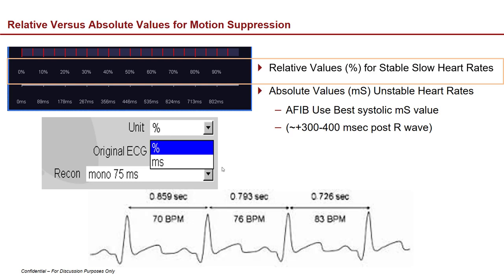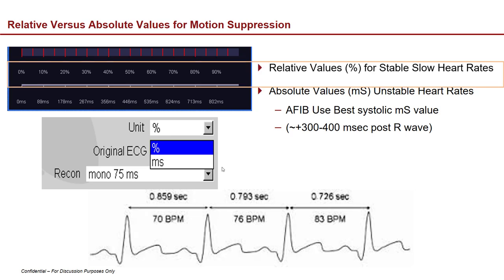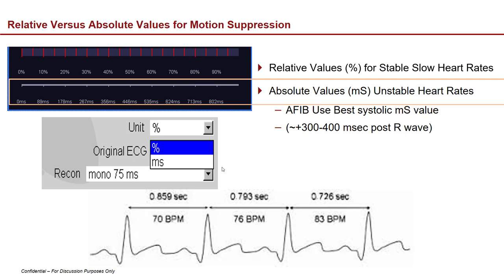For stable or slow heart rates, use percentage values to find diastole. Switch to milliseconds for fast or unstable heart rates — this identifies the best location because with an irregular heartbeat, it's the diastolic filling phase that changes, but the beat itself is relatively stationary and reproducible. If you count X milliseconds after the R peak, generally anywhere between 300 and 400 milliseconds, you'll get a better reconstruction.